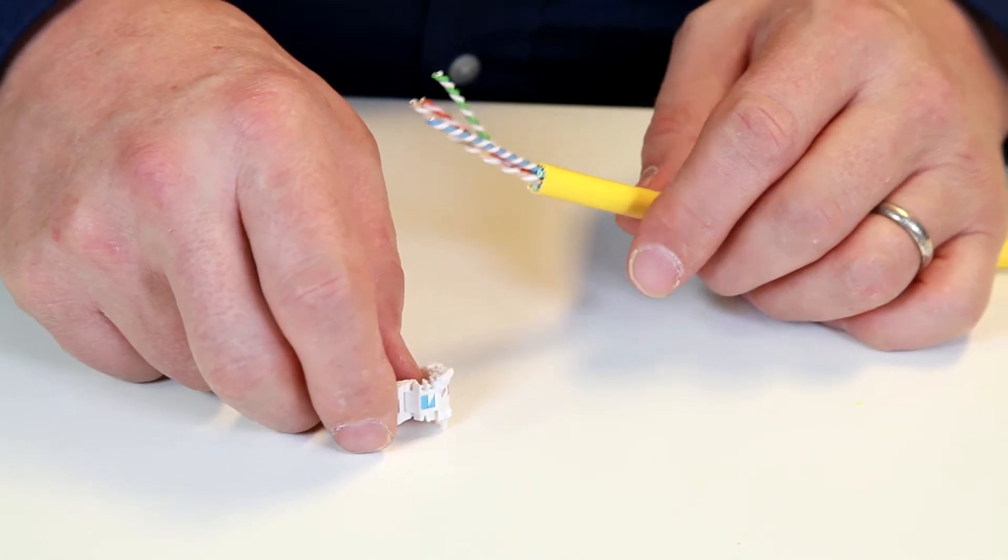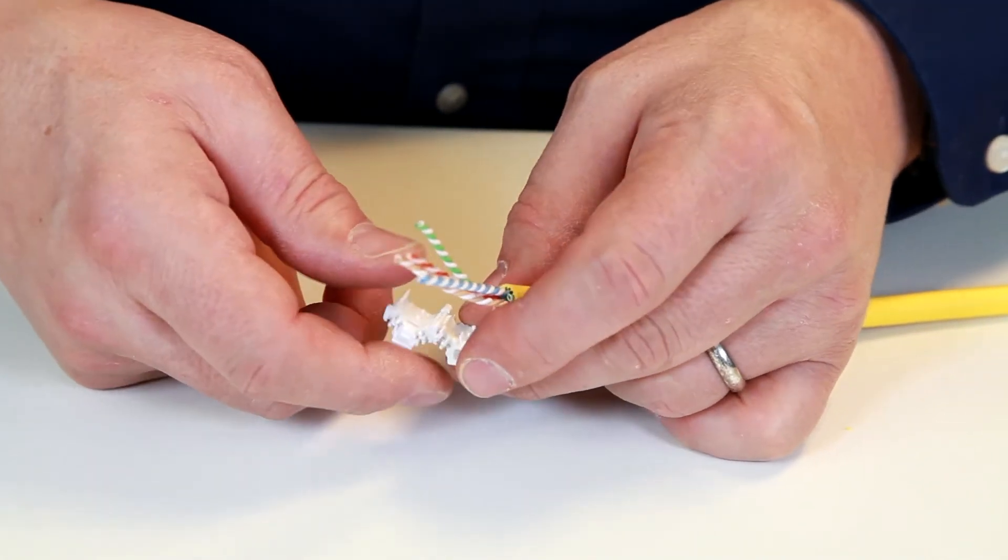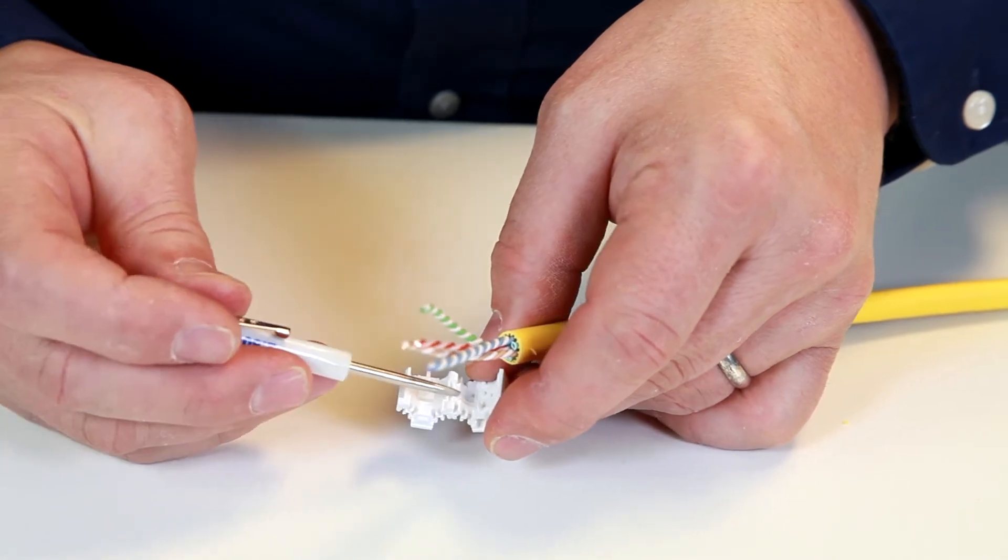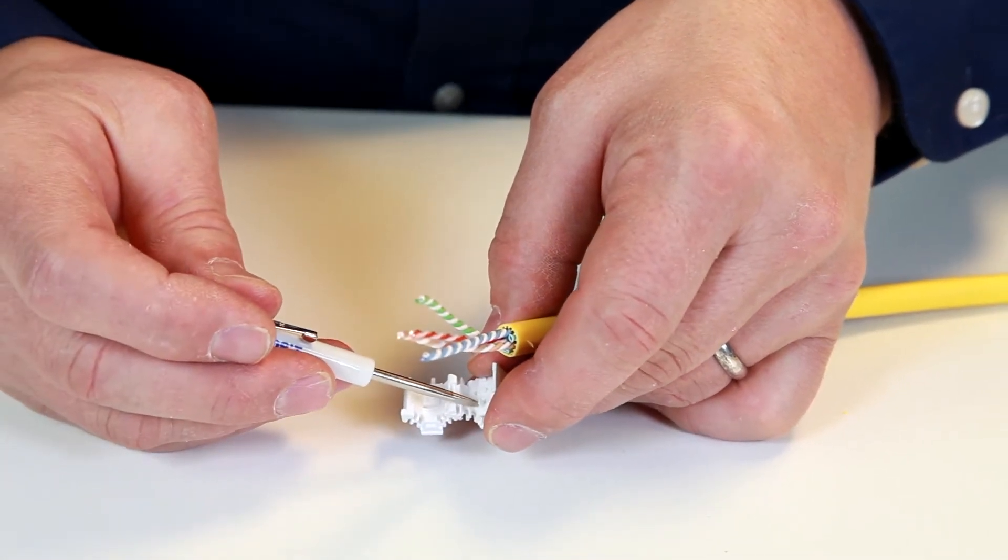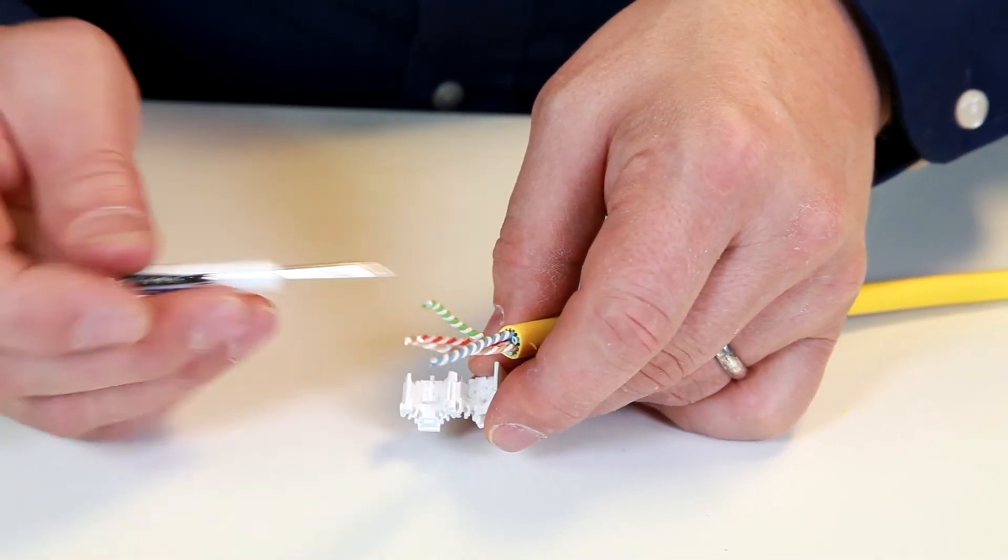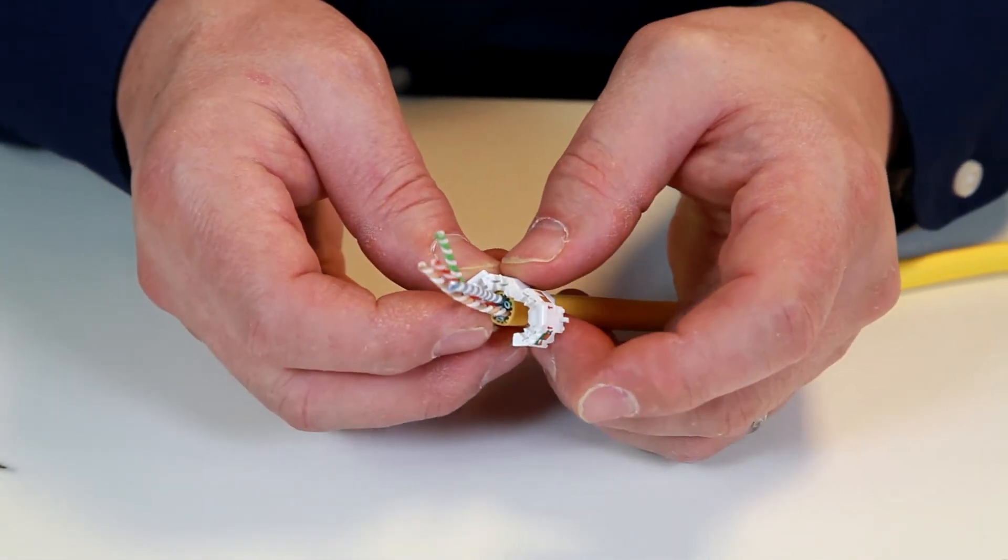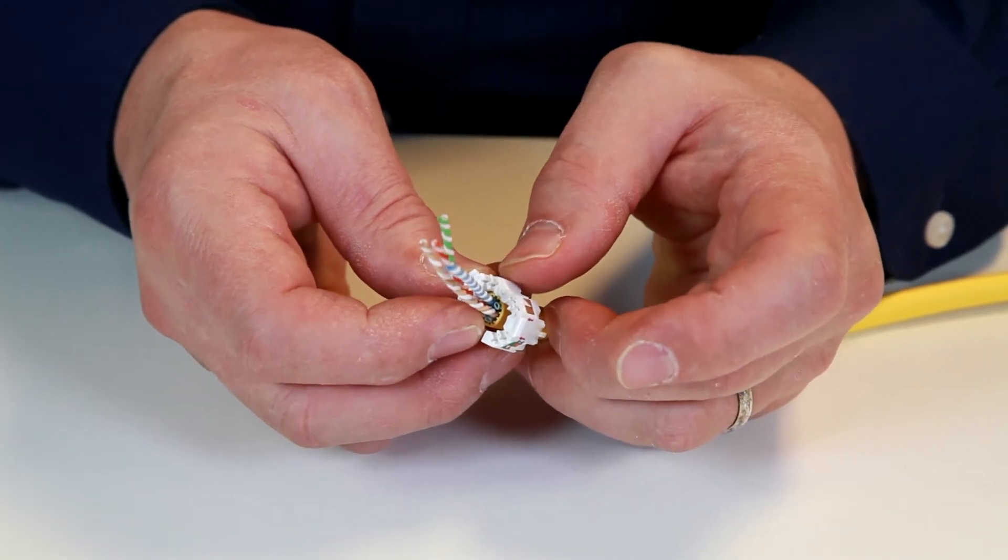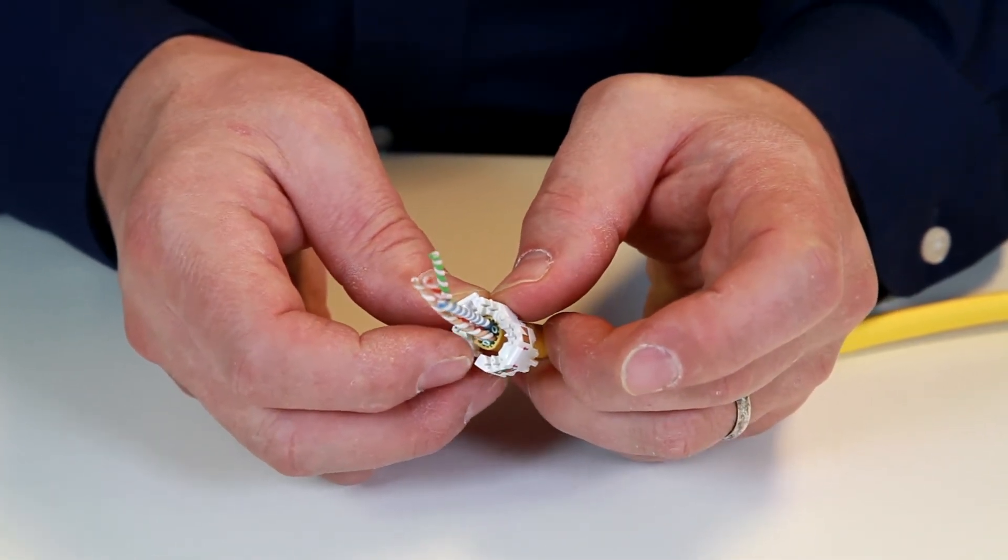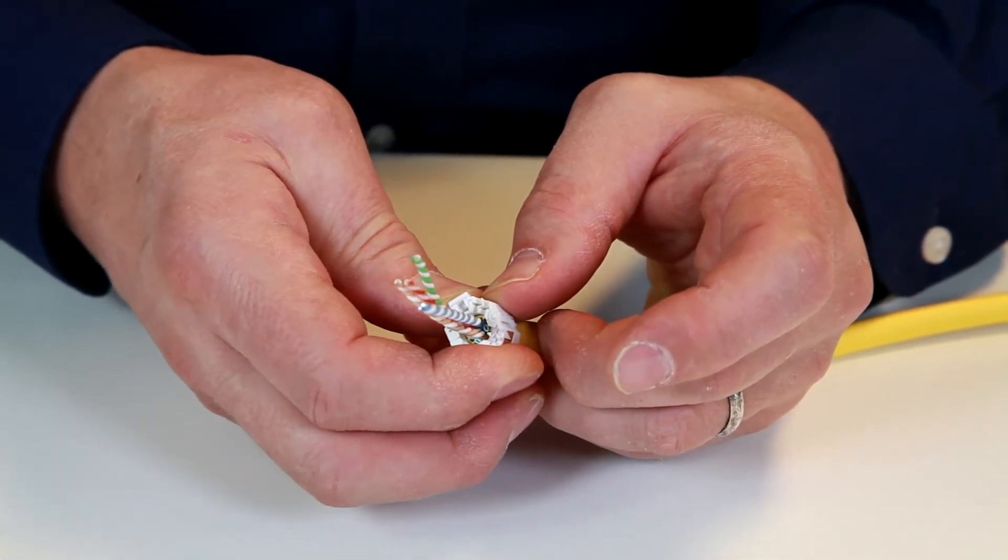Also inside the wire manager there is a cable stop right here, and the strip point of the cable jacket goes right at that stop. We'll line up the blue pair with the blue label, blue part of the label. Put the cable stop right down to the cable strip point and snap the wire manager closed.